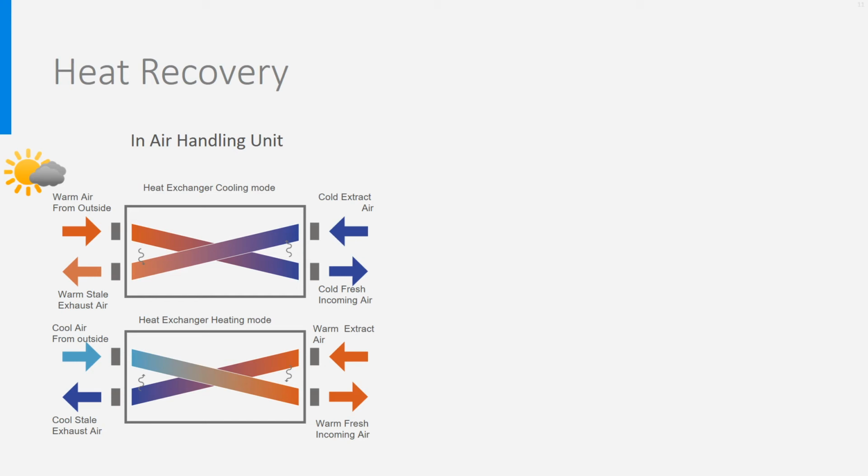This can reduce the heating and cooling needs in the ventilation itself by 60 to 80%, resulting at building level to a reduction of heating or cooling needs between 10 and 30%. To do so, you need pipes bringing the air into the heat exchanger and ventilators, which cost some electrical energy. This is not achievable with natural ventilation systems as there are no ducts.